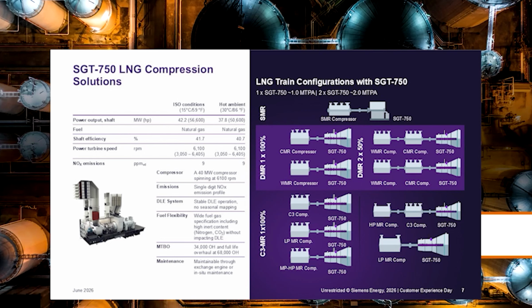And when you go into more of these a little more complicated cycles, you get a little bit more efficiency out of that. But in general, that's your nominal nameplate capacity. And your shaft efficiency on an SGT 750 at ISO conditions is around 41.7%. So I think that's industry leading efficiency for this type of turbine. Again, I mentioned the RPM for the power turbine at 6,100. That can be direct driven to the compressor. And our NOx emissions are at 9 ppm.